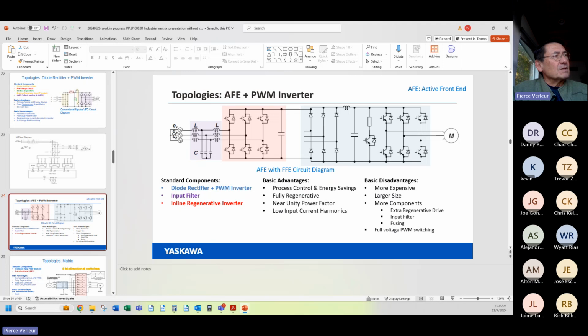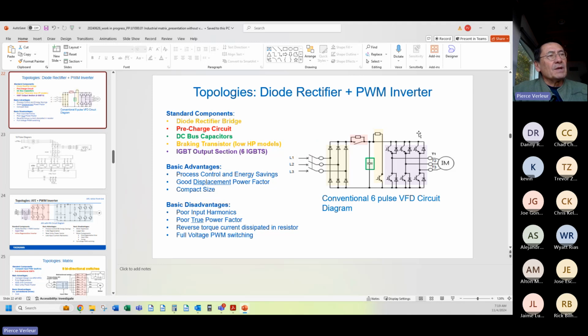In order to fix the problems going back to the line, which reduced the power factor, caused a lot of distortion, and common mode currents screwing up the ground plane, causing instruments to bounce all over the place, they came up with the active front end, which is nothing more than this section here of the original drive. This is the original drive, flipped around and connected so that it pointed back to the line. Bottom line here is, in this design, you can shape the waveform as you have to because you're putting a voltage and frequency out to the motor that's different from what you're getting from the line.